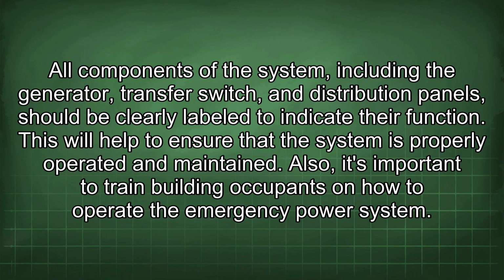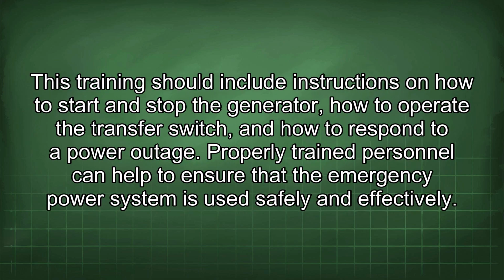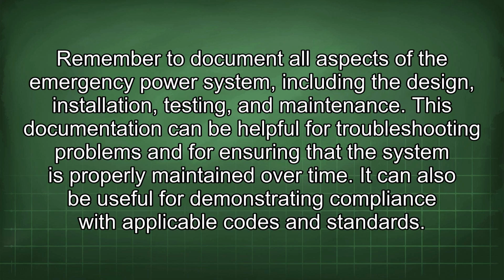Also, it's important to train building occupants on how to operate the emergency power system. This training should include instructions on how to start and stop the generator, how to operate the transfer switch, and how to respond to a power outage. Properly trained personnel can help to ensure that the emergency power system is used safely and effectively. Remember to document all aspects of the emergency power system, including the design, installation, testing, and maintenance. This documentation can be helpful for troubleshooting problems and for ensuring that the system is properly maintained over time. It can also be useful for demonstrating compliance with applicable codes and standards.